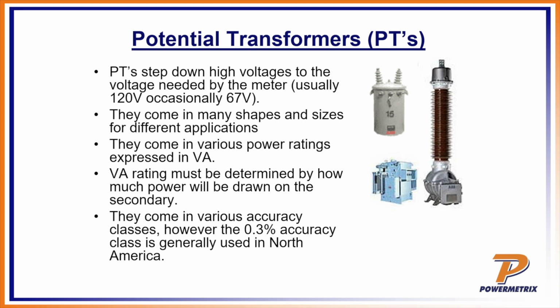They come in various accuracy classes. However, the 0.3% accuracy class is generally used in North America. Now remember, earlier we talked about the levels of inaccuracy added in. So remember, you're now adding in 0.3% accuracy. You're adding in some more. Yes, it makes it safer for us down at the bottom of the pole, but in a comparison between transformer rated and self-contained, you are unfortunately adding in some more inaccuracy, but it's making it a lot safer and easier to deal with.